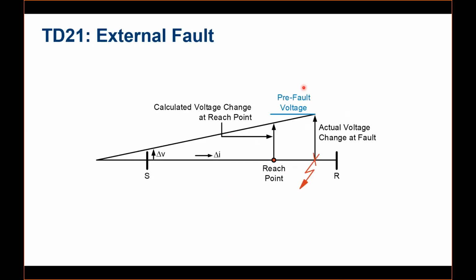Similarly, if you have a fault that is away from the reach point, the changes in the voltage and current samples will be such that the voltage change it calculates will be less than the pre-fault voltage. So this is the criterion by which we decide whether it is an in-zone fault or an out-of-zone fault. And this is not phasor based, so that's why it's much faster than the conventional distance protection relay.